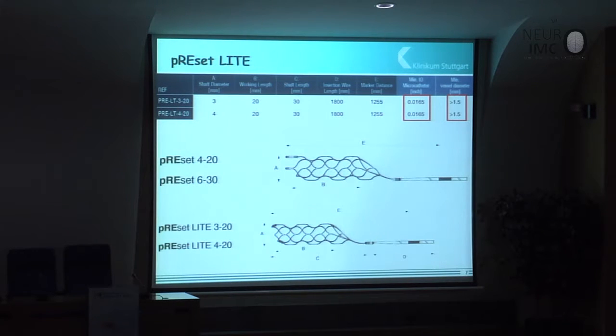The LT devices for preset are different from the regular device. One of the differences is that the regular preset has these kind of markers. These are the ends of the struts. Here, those are radiopaque markers. This is different for the low-profile device. For the low-profile device, the marker is integrated into the struts of the device. They are not these little pins reaching up distally to the device.